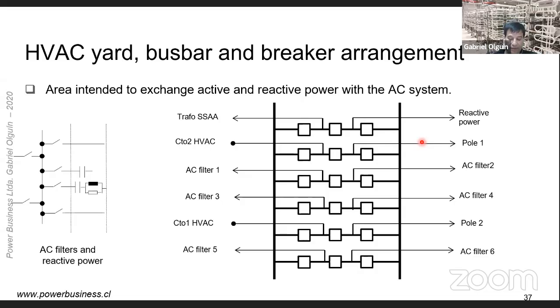The HVAC yard is the interface between the converter station and the AC system. Its objective is to enable reliable active and reactive power exchange with the AC system. LCC converter stations need reactive power compensation as well as filters. So this area is where this interconnection is done. The HVAC yard allows connecting all necessary equipment for proper control of active and reactive power exchange between the converter station and the AC system. Because of the massive power involved, the breaker bus arrangement must ensure high availability and maintainability. Typical arrangement is a breaker and a half arrangement for bus bar and breakers.